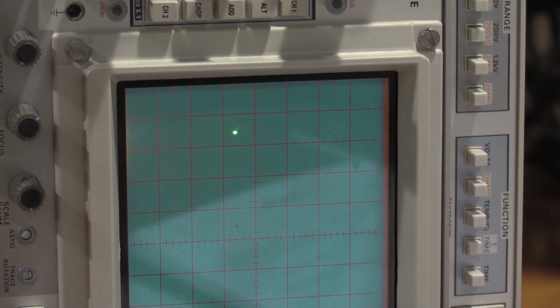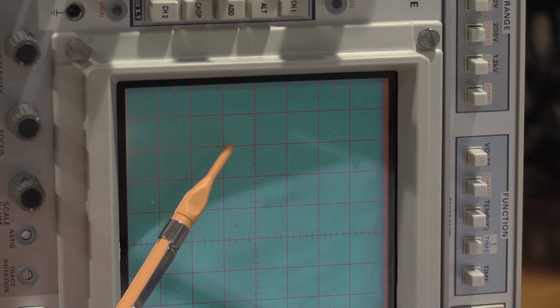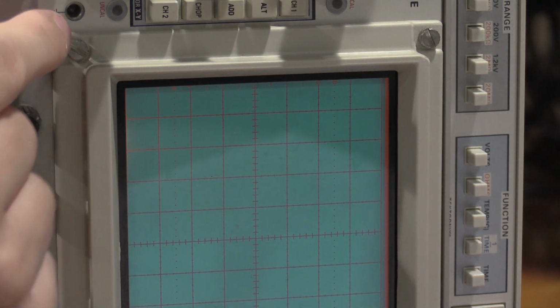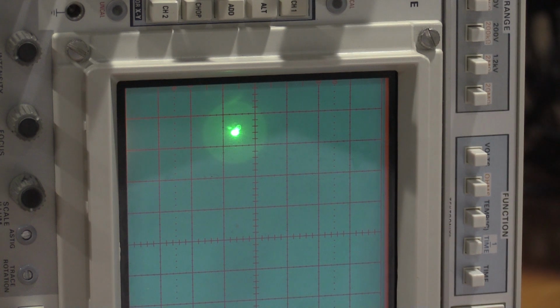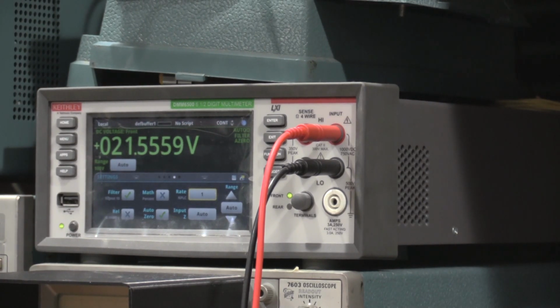So that's too much, that's brightening up. That right there to me is barely visible. You can actually see the camera can barely pick it up. But there's the spot right there. And now we go fully clockwise. And I'm supposed to have a reading of plus 20 to plus 30 volts, and I'm at 21.6. So we are good there. Turn that back down so we don't torture the tube. Oh, wait. Here we go. Beam finder. We do go up to 25. And now we turn it back down so we don't torture the tube.